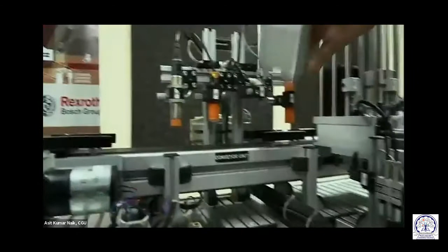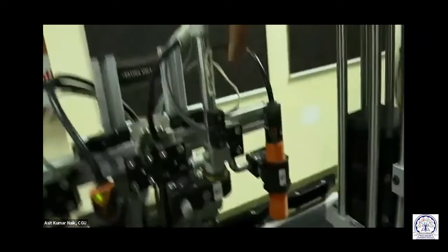Sir, do all the valves and all the cylinders have reed switches connected? Yes, for the magazine stations we have both reed switches, for extension and retraction, whereas for the cylinder present on this test unit, we only have one reed sensor, which is only capable of telling us if this cylinder is fully extended or not. We do not have a sensor to tell if it is retracted, because we do not need the other one. We require one reed switch over here to tell us if the object is in the correct orientation or not.